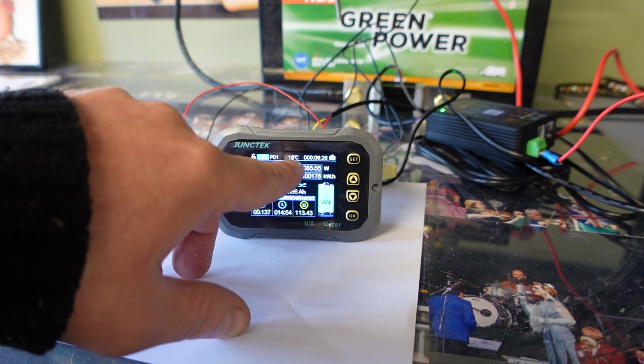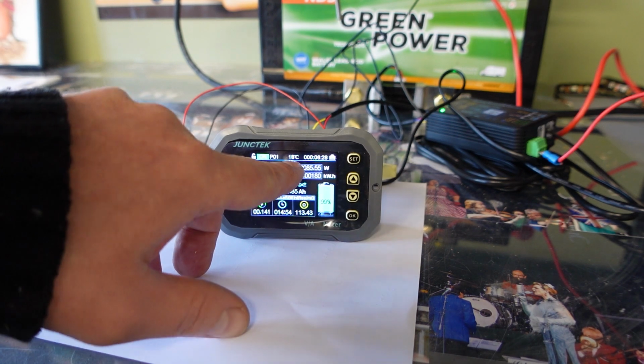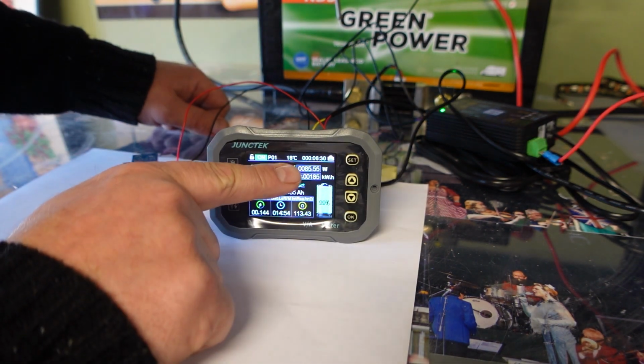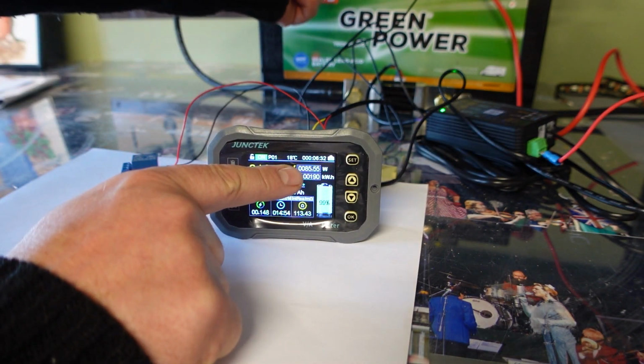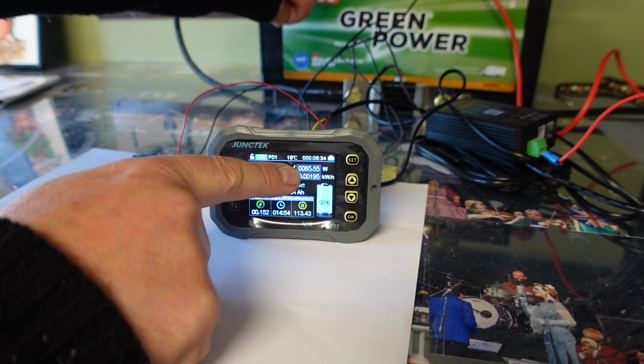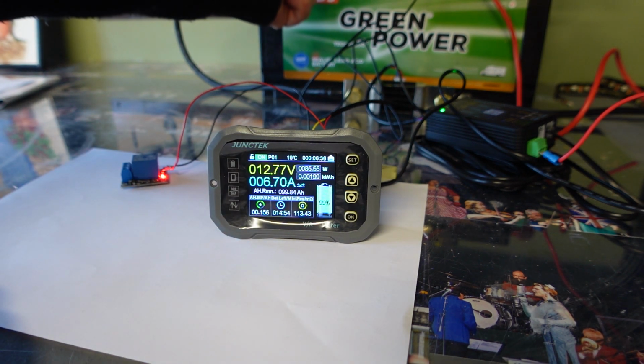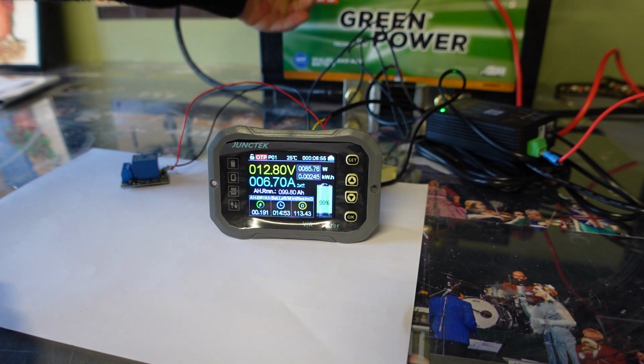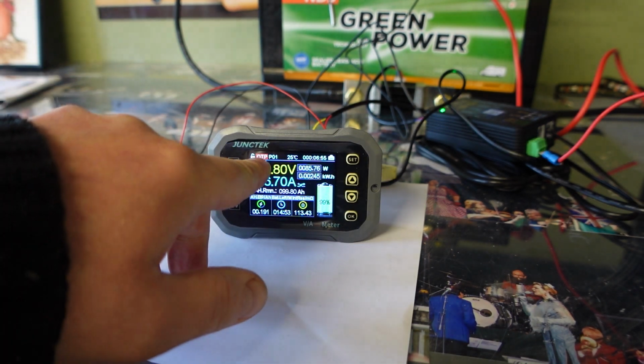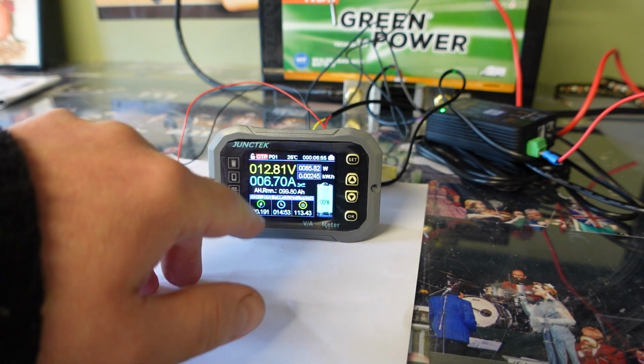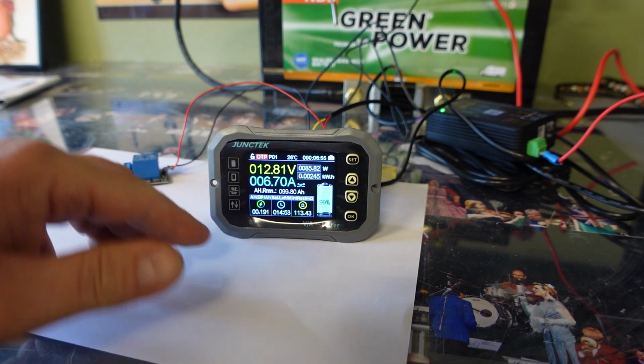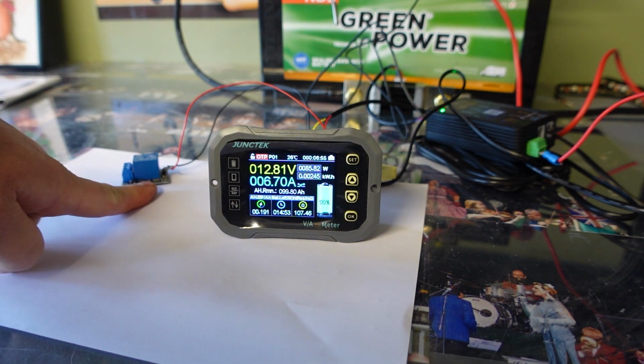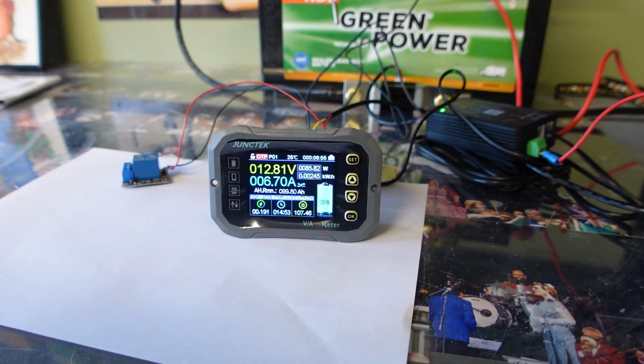Temperature's at 18 degrees on the gauge, so if you keep an eye on that temperature, if you can see it, I'll just leave my finger there so you can see it. I'll just put my finger on the probe, you see that temperature go up and it'll go into protection. 19, 20, need warmer hands. Right, there you go, it's now gone red on there for over protection, and padlock, I don't know whether that means it's disconnected, but you can see the LED on here has also gone off. We're at 26, 25 now.